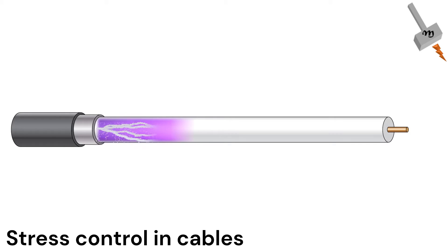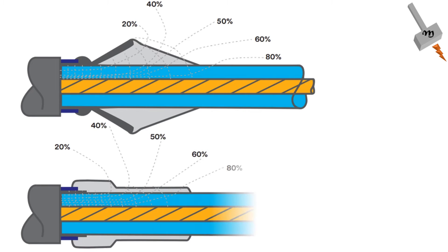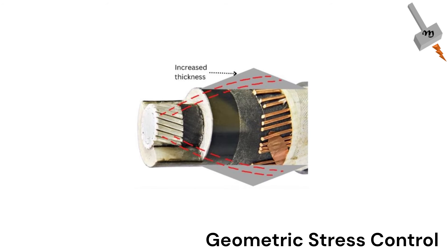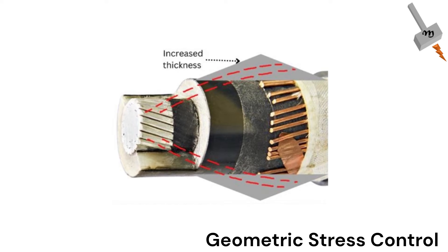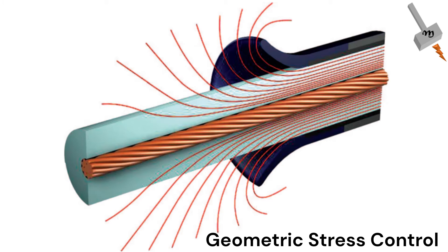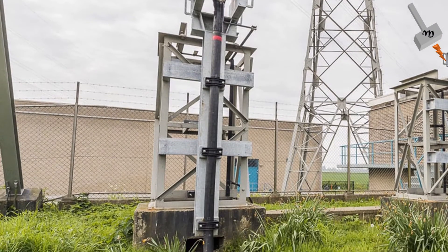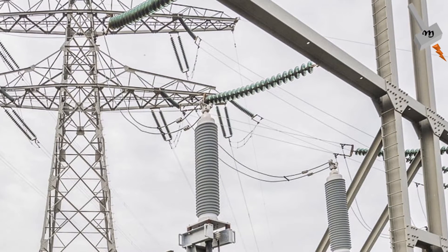There are two common methods for stress control. The first is geometric stress control and the other is capacitive stress control. The geometric stress control method increases the effective thickness of the insulating material near the shield discontinuity — this is the method used from the early days of cable terminations. The cone-shaped component forces the electric field stress to spread out more evenly, thus reducing the stress at the discontinuity. A disadvantage of geometric stress control is the thicker profile, limited bend flexibility, and difficulty of installation.